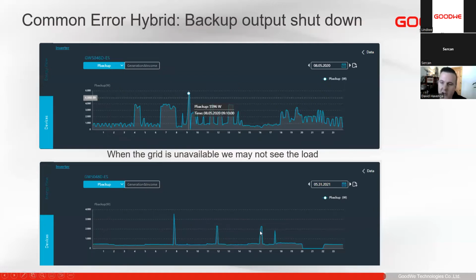But unfortunately, when we only have batteries available and our discharge limit is set as it is, that load won't run for an extended period of time before it shuts down. It will shut down almost immediately if we're exceeding the battery discharge limits, and then we won't see the load. In the back end, we can see that it gives some error, almost like a short circuit, because of a sudden load that's too big for the backup or the batteries to handle.